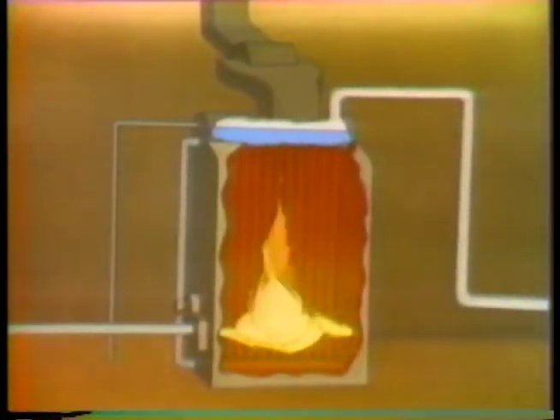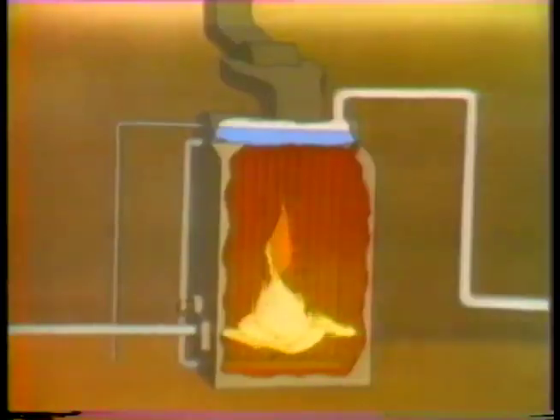As the flue gas moves through the furnace, it transfers more and more heat to the boiler tubes, and the gas temperature drops. As the tubes absorb heat, the gas loses heat. Then conduction carries the heat through the tubes to the water, where the heat turns the water into steam. Also, considerable heat is provided by radiation from the boiler flame. In this way, all three methods of heat transfer are used to create the final product of the boiler, steam.